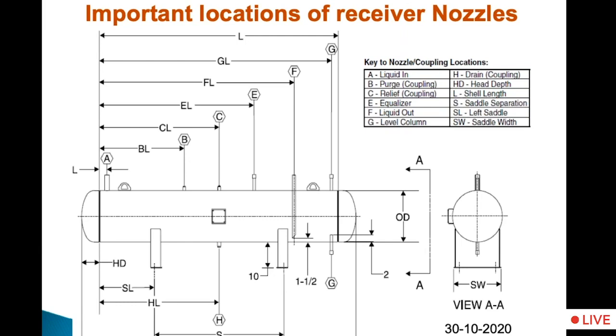There is a relief valve, that is a pressure relief valve on the vessel, which is normally used as a dual pressure valve. Equalizer connection: if you are using two ammonia receivers, then the pressure in both the receivers needs to be equalized. So there is a gas equalizing line and a liquid equalizing line. There are two connections for pressure equalizing. Then there is a liquid outlet and a level column, a level indicating gauge glass.